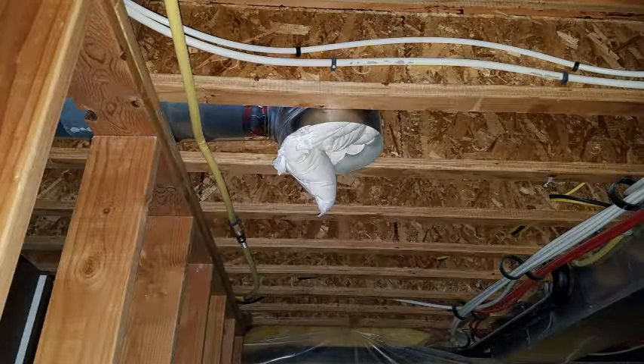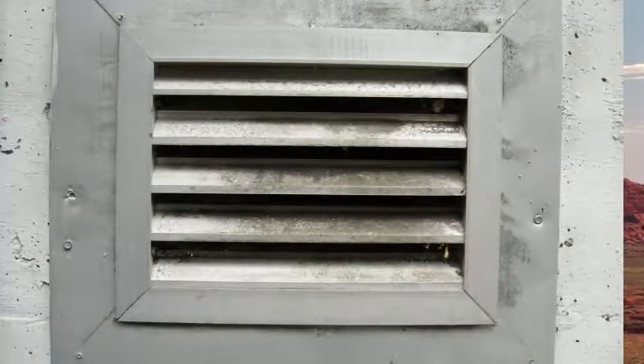And now if we've got the fireplace on too, then instead of air leaving the home, you've got this backdraft coming into the house. And that backdraft is carrying all the carbon monoxide that should have been leaving the home, but is not. So under these sorts of conditions, you've got a potentially deadly environment, and the homeowner would never think, for example, that having the bathroom fan on, or other things like the dryer, could actually create a deadly condition. One answer to that is actually to have the combustion air source, which is required for all newer homes.